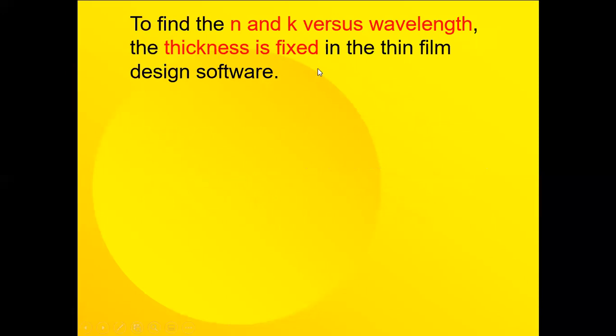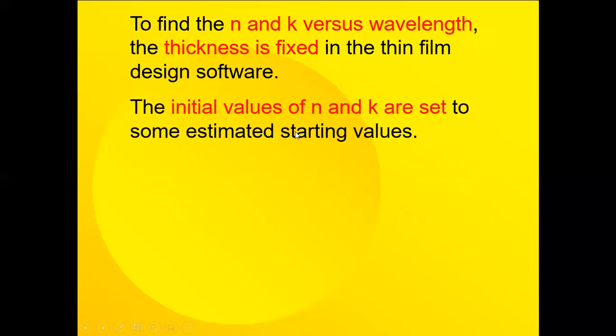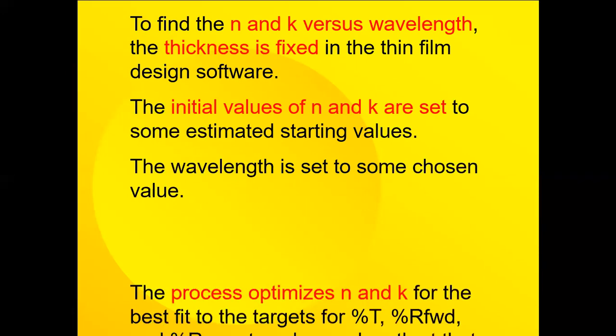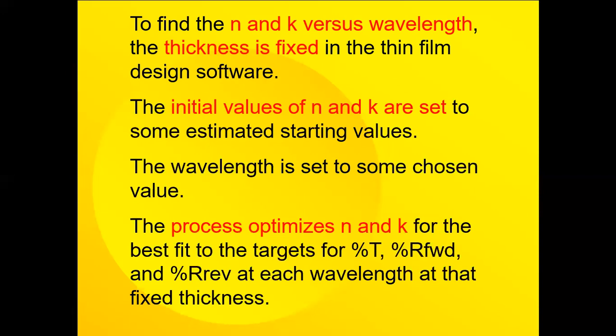To find the N and K versus wavelength at these measured wavelengths, the thickness is fixed at the value which we just found. Then the initial values of N or K are set into the software as estimated starting values, and then we optimize for a given chosen wavelength. So we have the three data points for two reflections and transmission, and the process optimizes for N and K for the best fit to those targets.